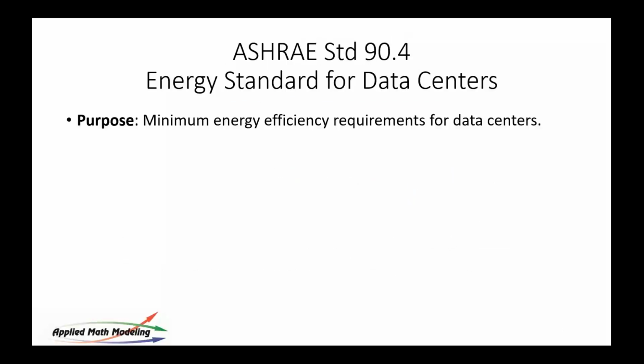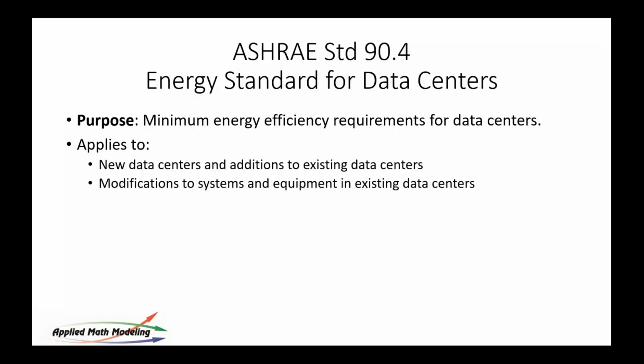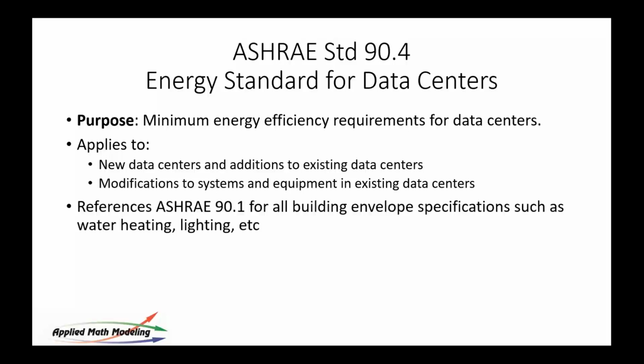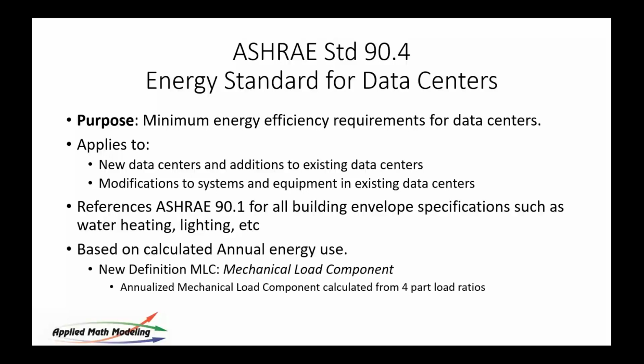So if you look at 90.4, it's a minimum energy efficiency requirement for data centers. It applies to new data centers as well as existing data centers. It applies to modifications to data centers. It references 90.1 for all building envelope specifications. 90.4 was an extension to 90.1 because ASHRAE realized that there were data centers in some of these buildings. How do you handle LEED certification on a building that's got a data center in it? That was the fundamental question.